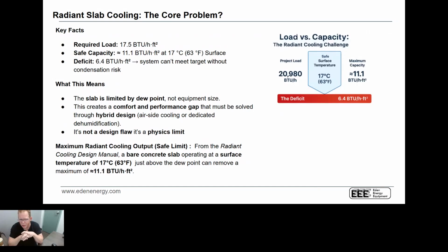Well, the challenge with that is if you look at the design manual, the radiant cooling design manual that will be emailed to you guys, you'll discover that typically we're only going to be able to pull about 11 BTUs per square foot out from a radiant cooling from the standpoint of the sensible energy. And that's also assuming that we're doing it where we don't drop below the dew point. So what we're looking at is we want to make sure that we have cold enough water that will cool the space, but not so cold that it's going to cause the floor to condense.